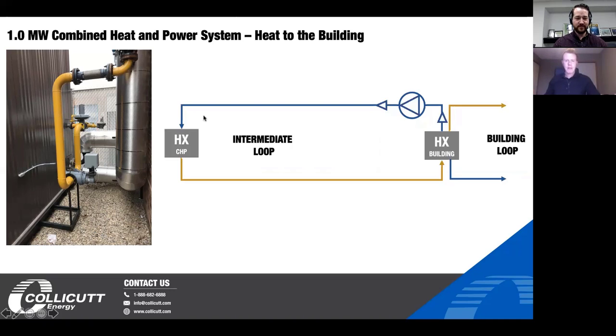And effectively what's happening is that CHP heat exchanger that we saw on the previous slide, we've taken the heat from the engine and the jacket water, it's been consolidated, and now we're flowing that fluid back through the heat exchanger and back to the building. The heat loop at Red Deer College is actually, I think, 1,500 feet long, the whole loop. Oh, wow. So it's an incredibly long loop. And then on the building side, we have another set of heat exchangers where we are transmitting the heat from this intermediate loop to the building loop.